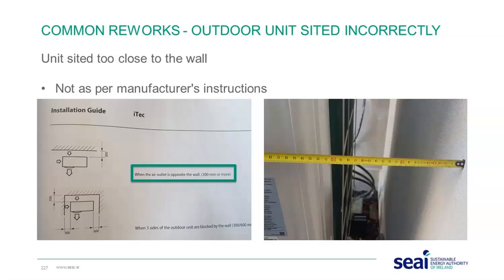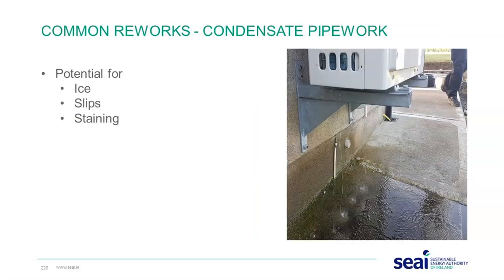Again, it's a heat exchanger. We want to get a good rate of exchange, and if the air can't flow through it because it's too close to a wall, the system won't work as efficiently. So in this case, the inspector will highlight it, and you will receive notification requesting you to go out and move the unit out in accordance with the manufacturer's recommendations.